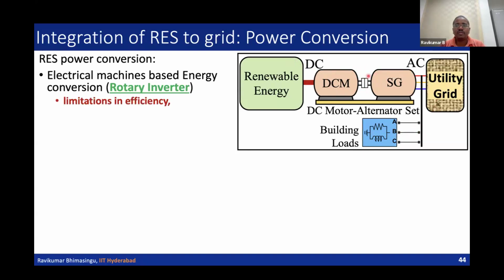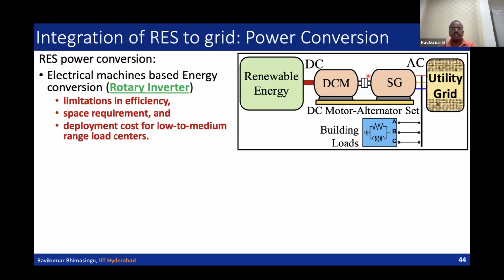The problem with this type of conversion is limited efficiency, since you are using real rotating machines whose conversion efficiency is limited, along with space requirements. For small conversions like 10 or 20 kilowatts it's fine, but to convert a few megawatts, the size of the DC machine and synchronous generator increases. Whenever there are space limitations, especially at high load centers, this becomes very difficult, and deployment cost for low to medium range load centers is higher.